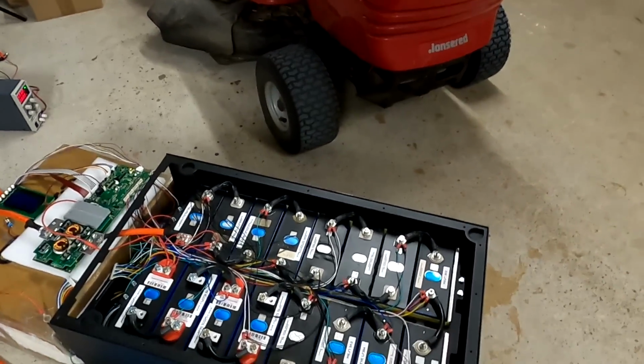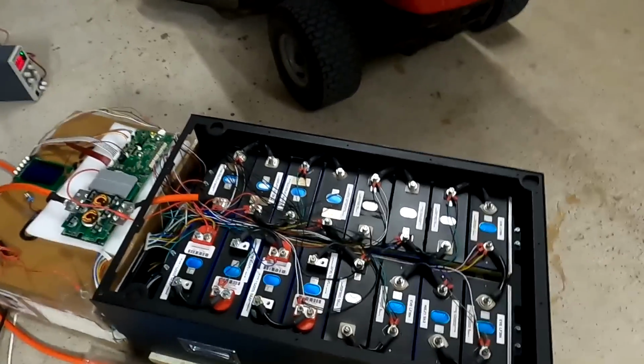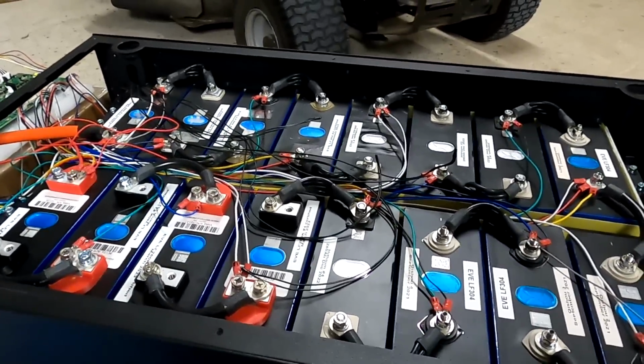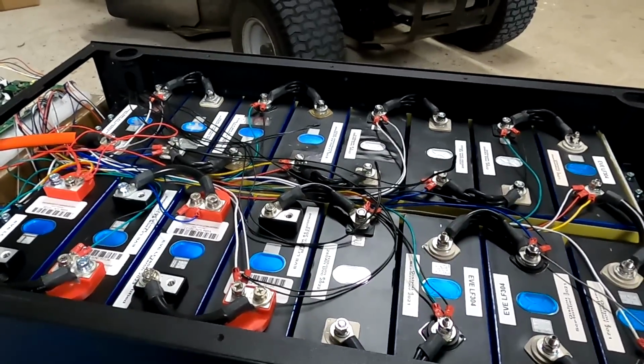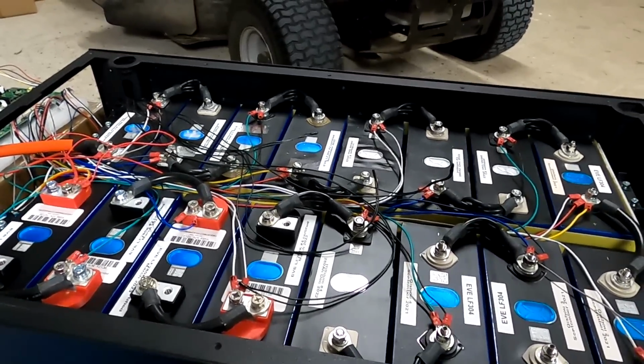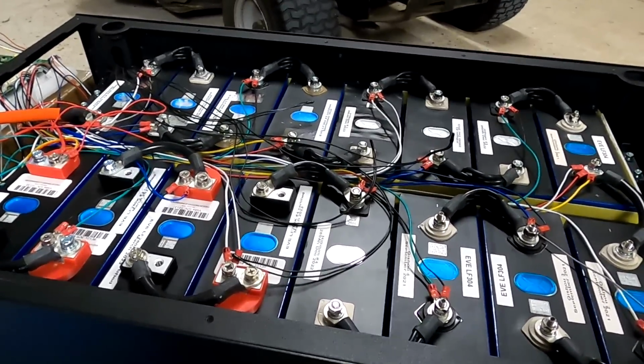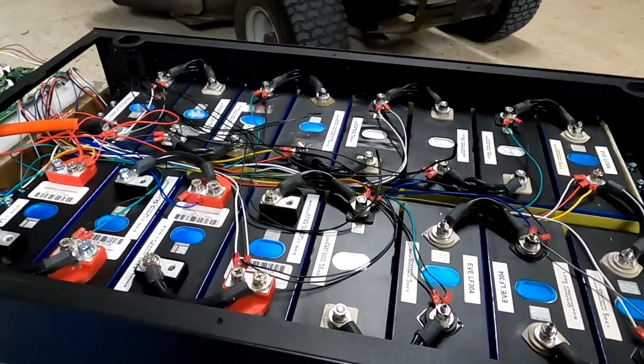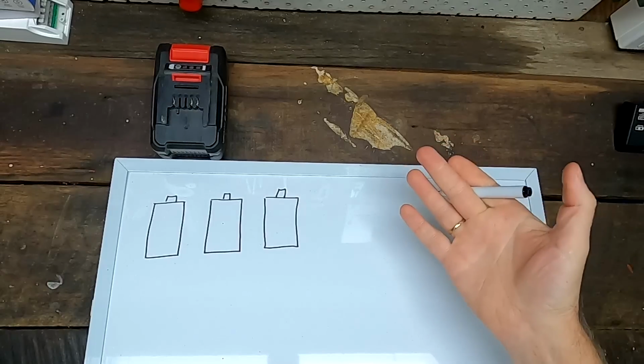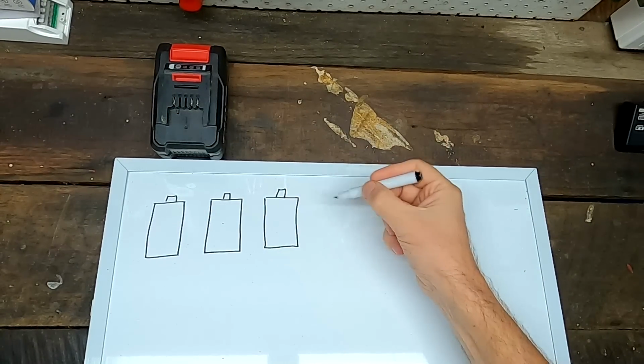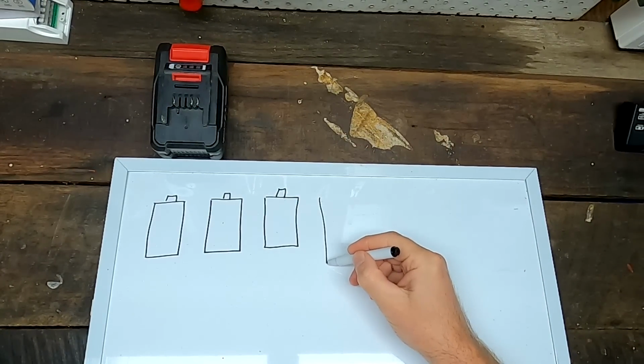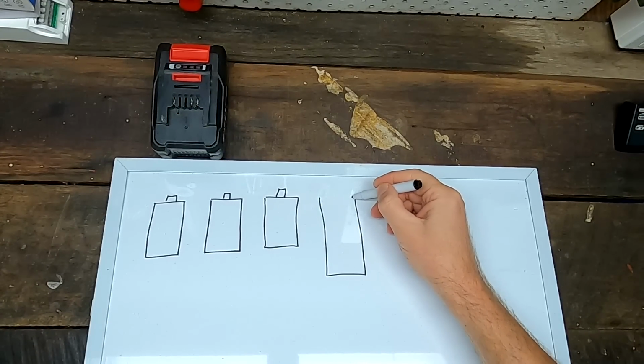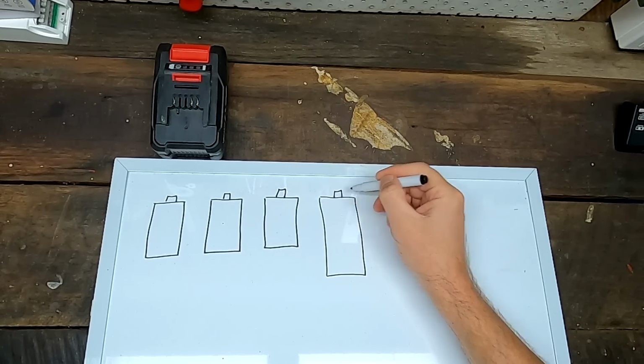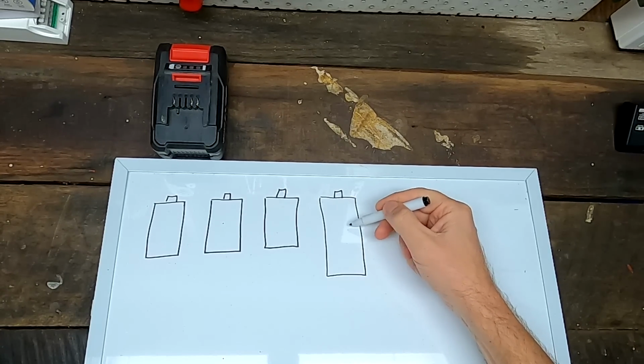Because we have a mix of 280 and 304 ampere hour batteries here, obviously we cannot discharge the battery any further than 280 ampere hours, and the 304 ampere hour ones will have a bit of rest capacity left at this point in time. So here's quickly what we have: 3 of the same batteries, and one of the batteries is a bit higher—so this one has more capacity.